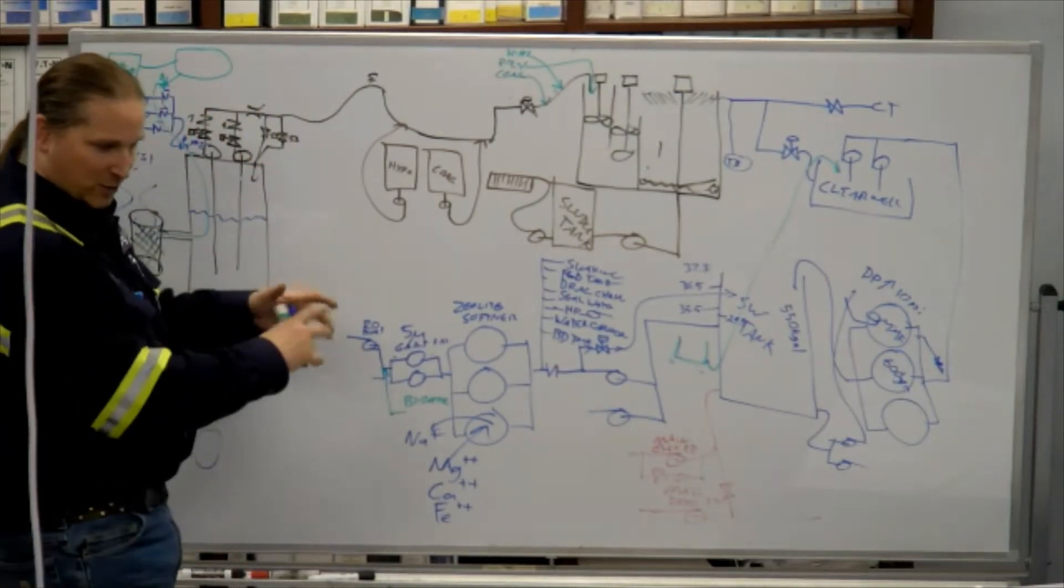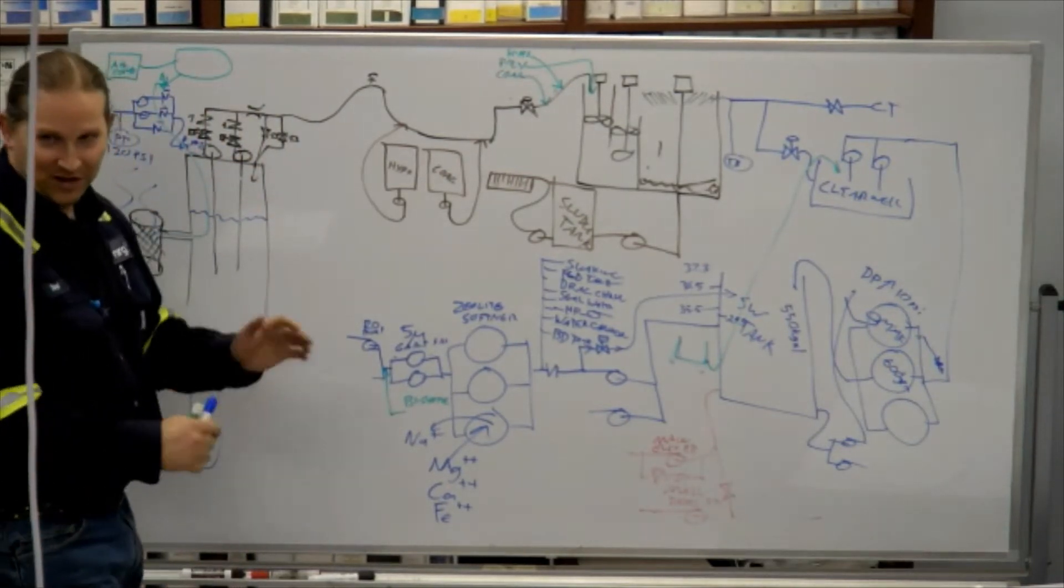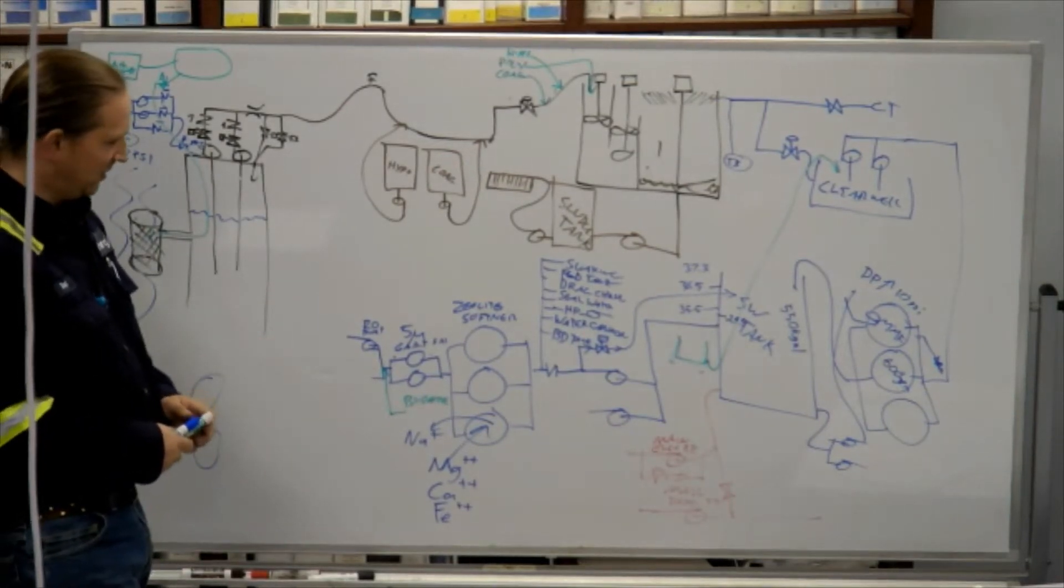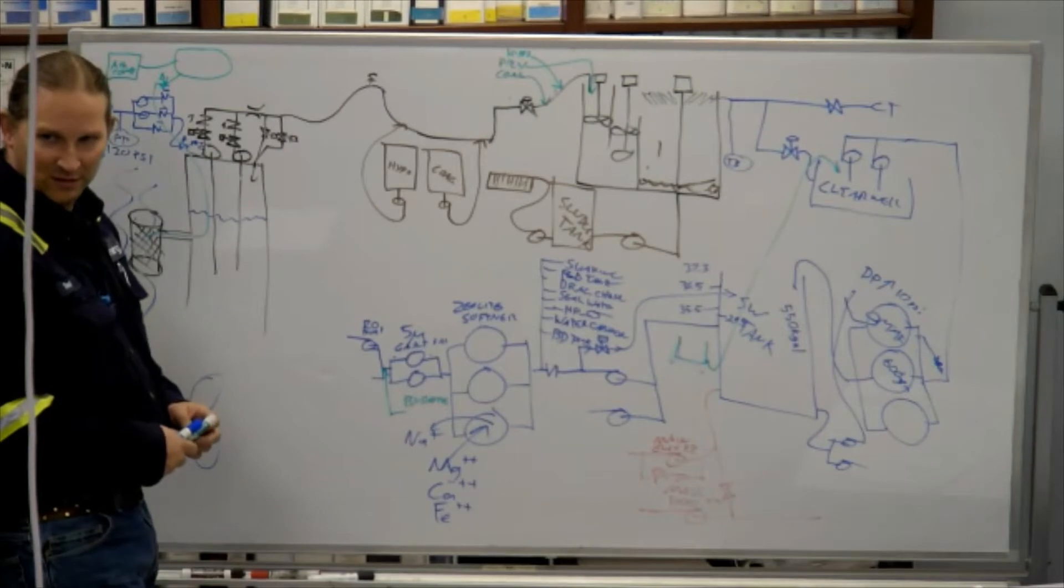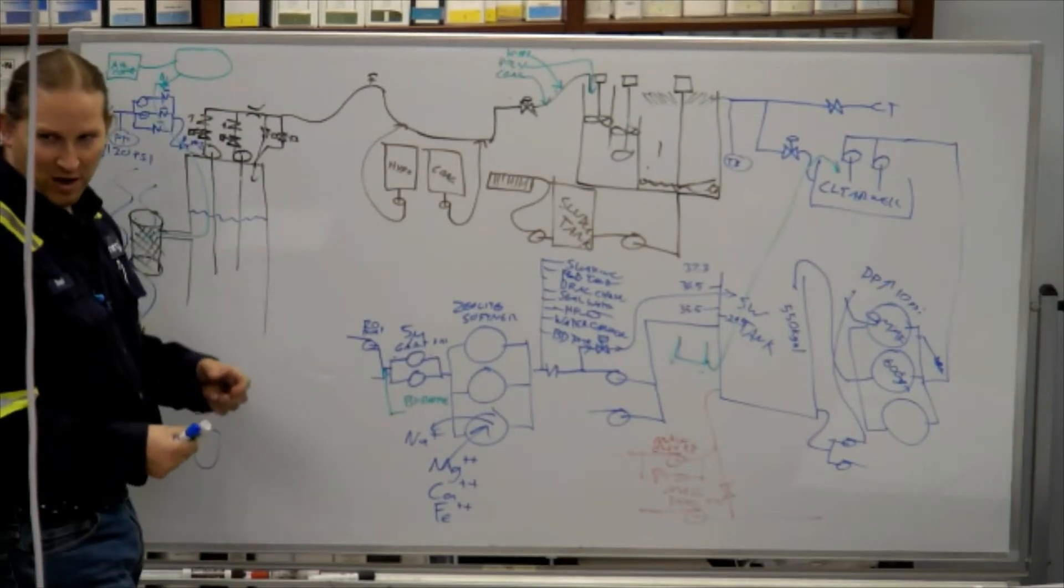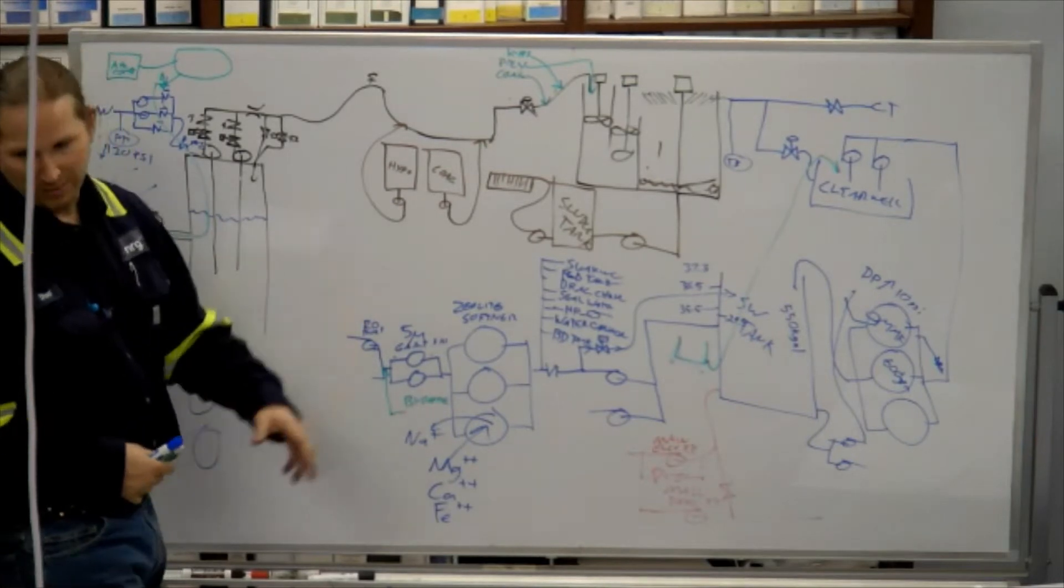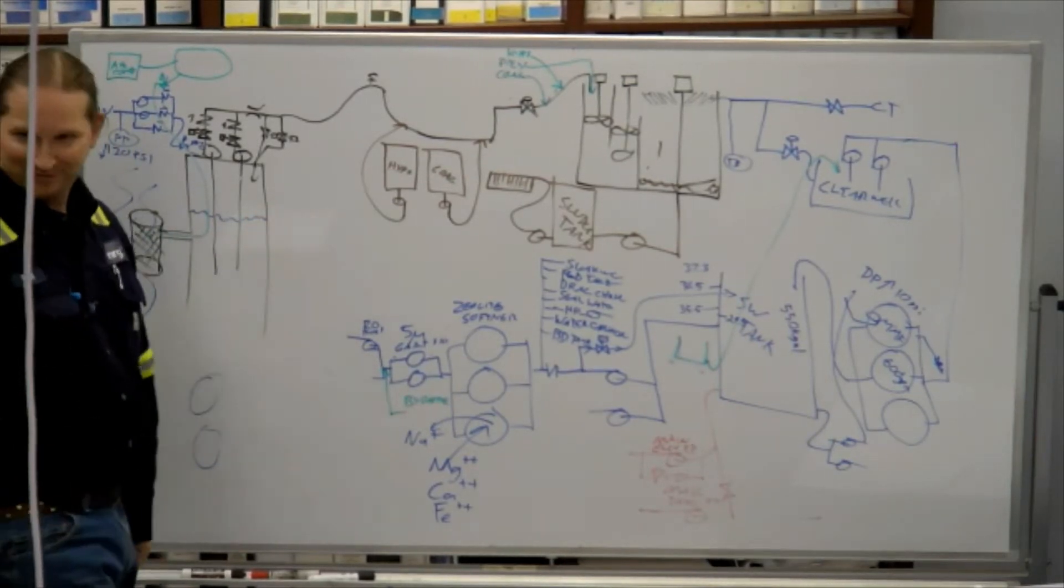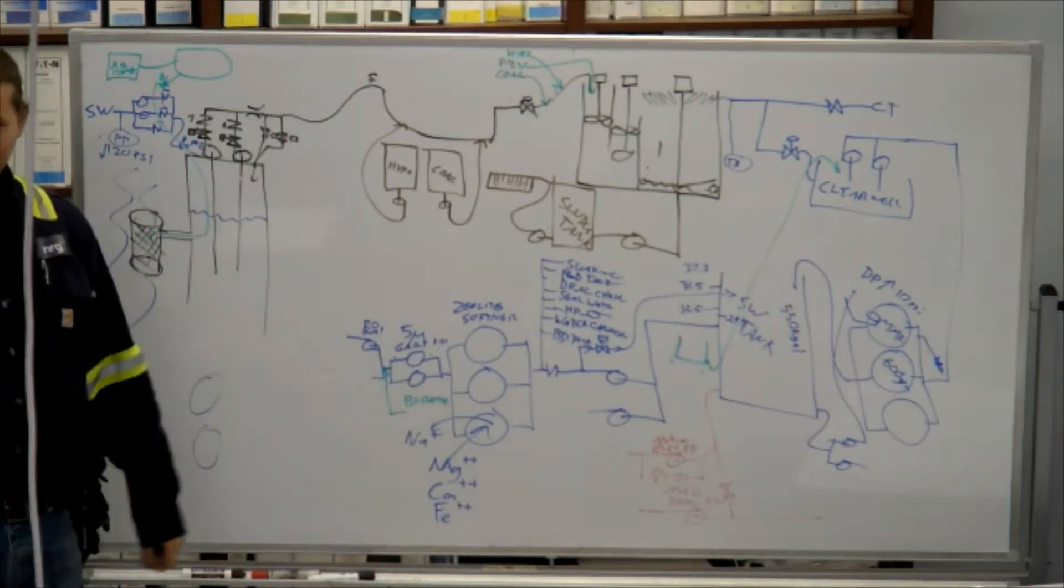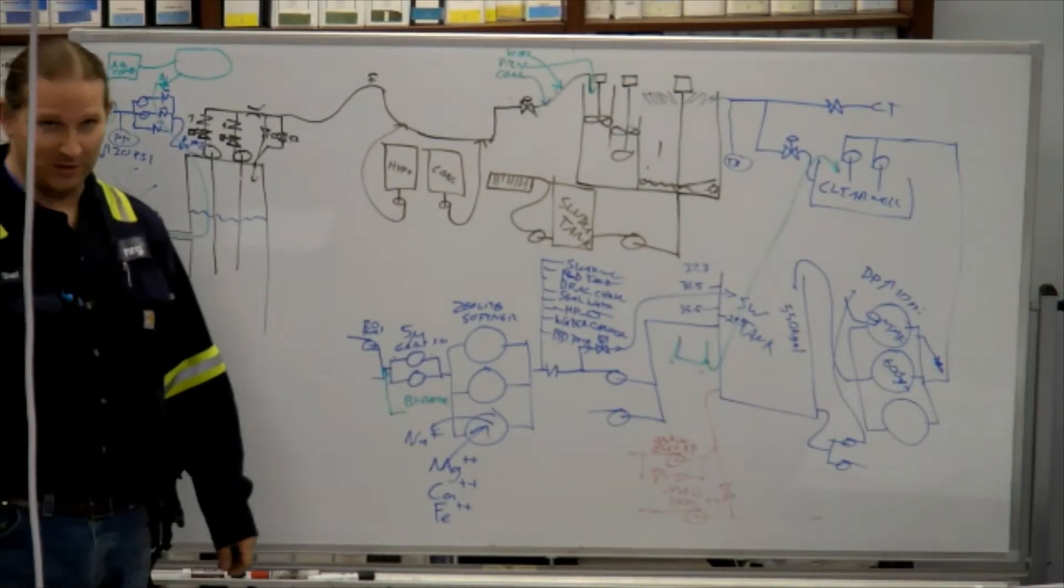So bisulfite bonds together with hypochlorite and makes it inert, so it quits interacting with things. Alright. Does the hypo mess up the filters? The RO membranes, they wear out faster when they're exposed to hypo. They get brittle. I use quotes a lot when I'm talking about things I don't really understand that I'm taking other people's words for it.